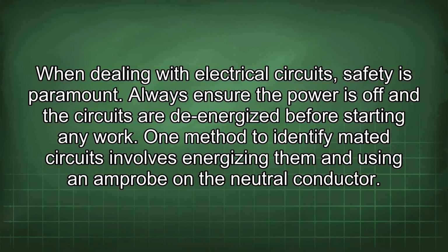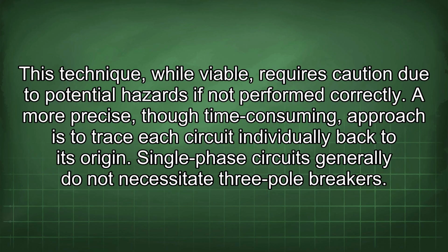When dealing with electrical circuits, safety is paramount. Always ensure the power is off and the circuits are de-energized before starting any work. One method to identify mated circuits involves energizing them and using an amprobe on the neutral conductor. This technique, while viable, requires caution due to potential hazards if not performed correctly. A more precise, though time-consuming, approach is to trace each circuit individually back to its origin.